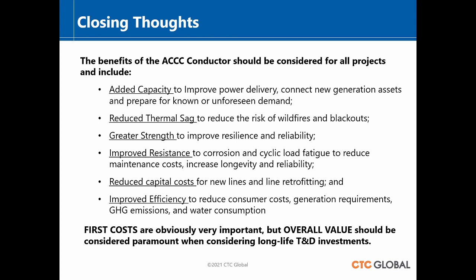Reduced thermal sag, which we're seeing in Southern California. Because the sag is so much lower, they stay up out of the fire zone, and that's a resilience issue. They don't sag down into the zone, they don't get heated up and become part of the problem, and they're ready to return to service without being annealed or overheated and having to be replaced. They now provide a resilience and reliability benefit to you.